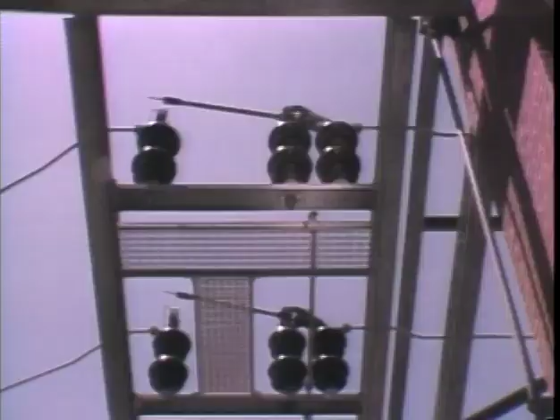Disconnect switches are used primarily to isolate a circuit from its power supply once the circuit has been de-energized. Isolating is a secondary protective measure. It creates a visible break in a circuit so that if the circuit breaker is closed accidentally, the circuit remains de-energized. Breaking a circuit under load can be dangerous, particularly if the circuit is carrying high voltage. That's because there's an increased chance of arcing when high voltage circuits are opened. Arcs can cause fires, injure personnel, and burn up equipment.